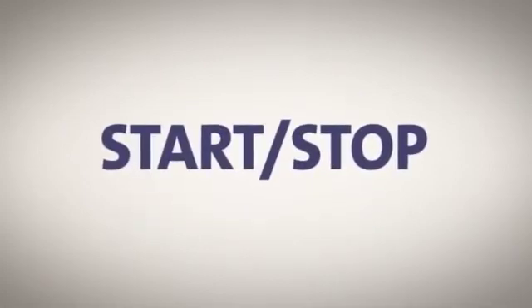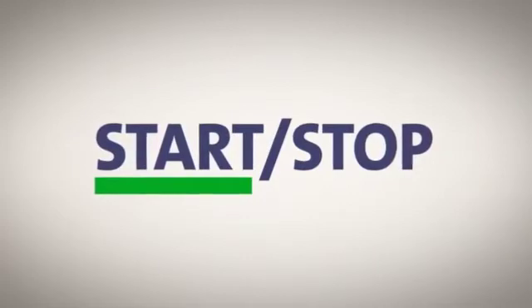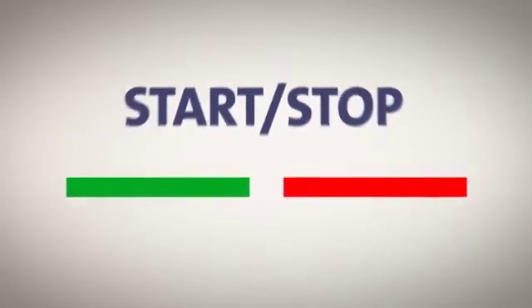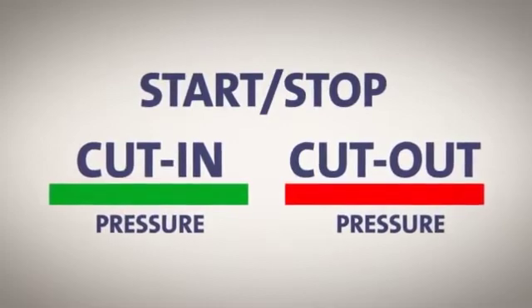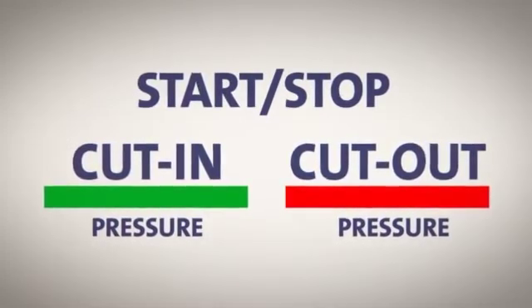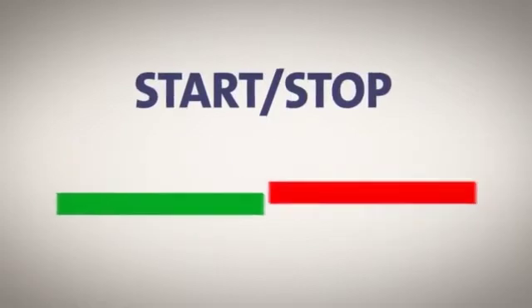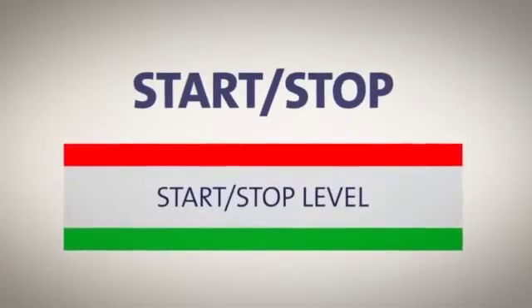With a start-stop solution, the booster pump starts and stops according to a predefined cut-in and cut-out pressure. And how do you define that? The first step is to calculate the building's required minimum pressure in order to be able to set the start-stop level.